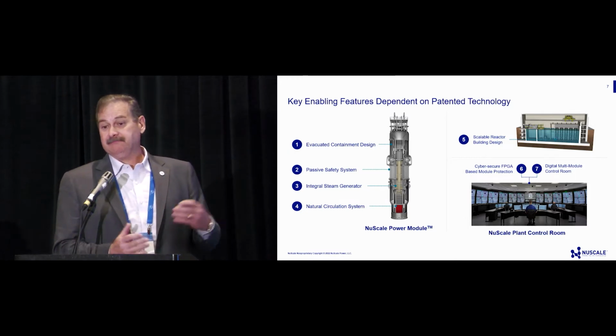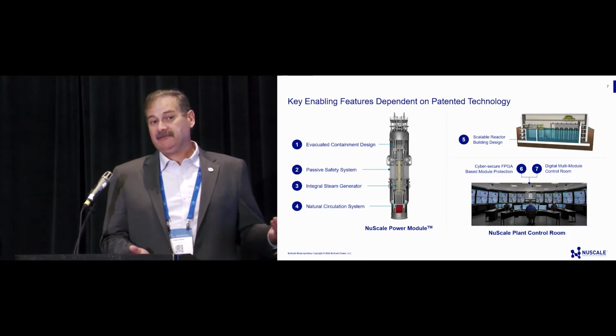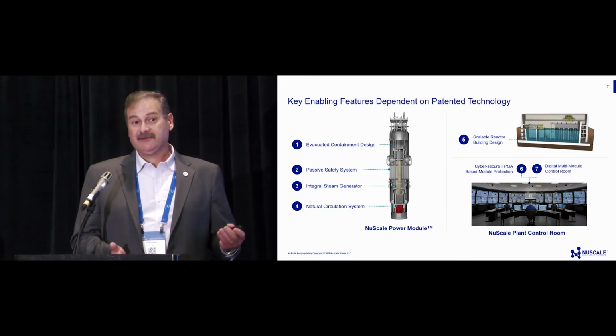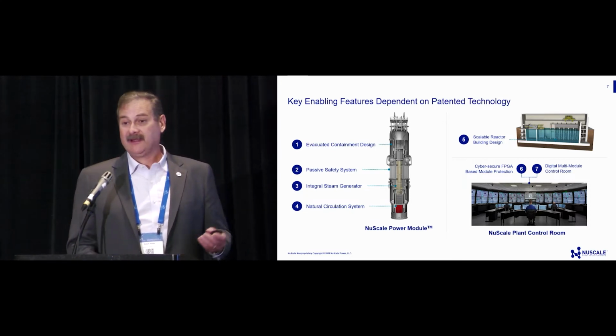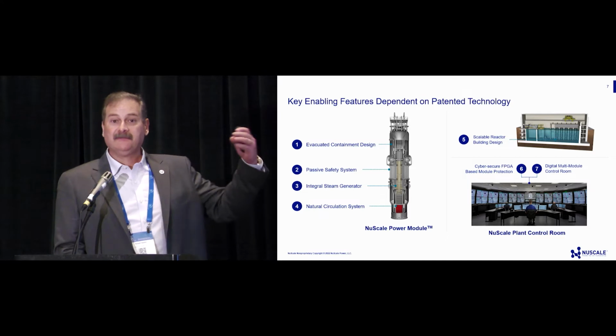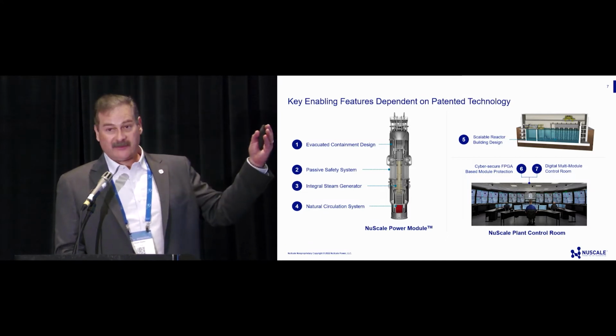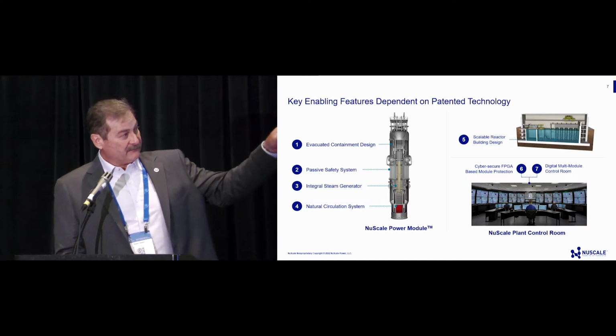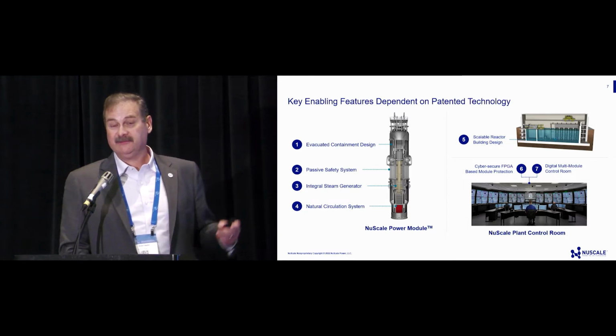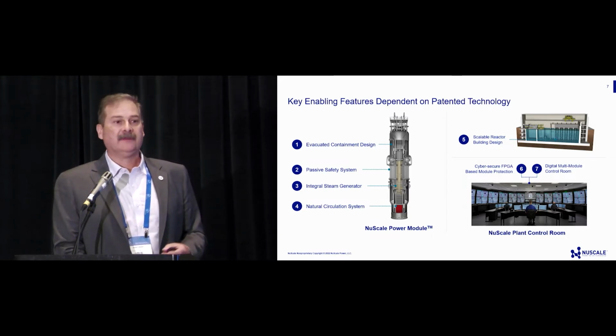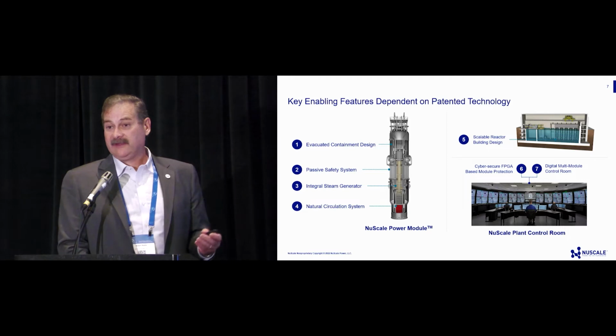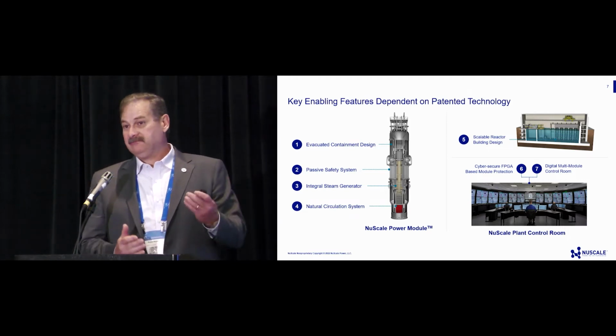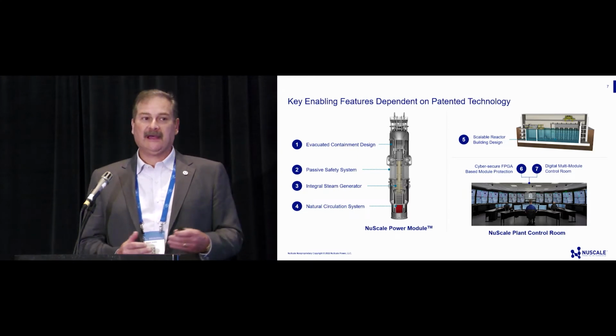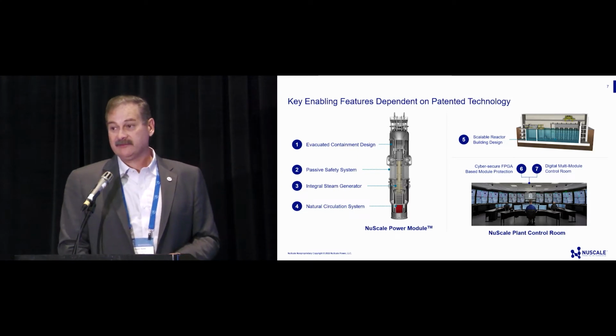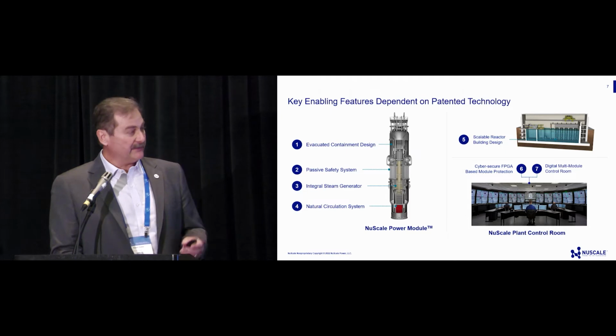When the fuel was expended for the uprated module, it's about 18 months of operating time. You would shut down the module, disconnect it, pick it up with a crane, move it over to where you, right underneath the yellow machines, where you would disassemble it and refuel it. The other remaining units would stay online at 100%. So your total loss would be 77 megawatts for the outage duration, which we're now scoping for 10 days for the refueling outage.